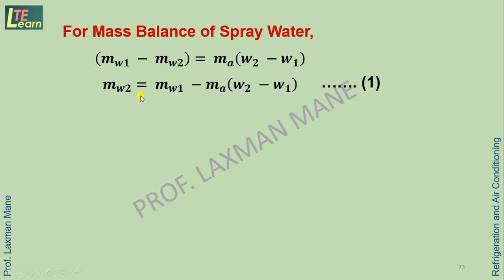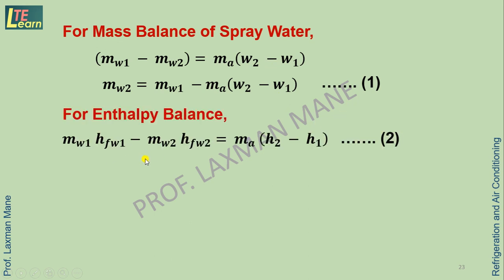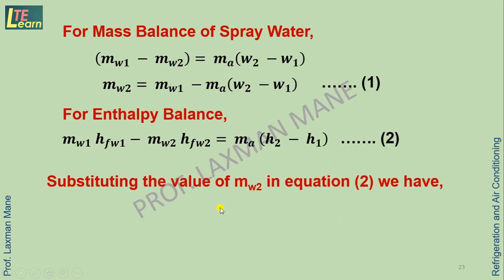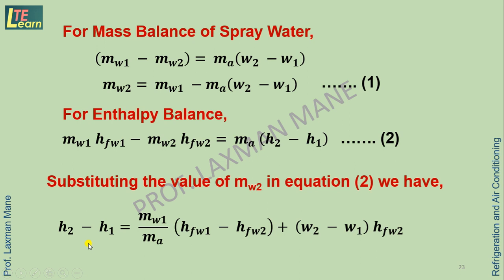The mass balance equation for the heating and humidification process with spray water is: Mw2 = Mw1 − Ma × (W2 − W1). The enthalpy balance is given as: Mw1 × hfW1 − Mw2 × hfW2 = Ma × (H2 − H1). Substituting the value of Mw2 from equation 1 into equation 2, we get: H2 − H1 = (Mw1 / Ma) × (hfW1 − hfW2) + (W2 − W1) × hfW2.